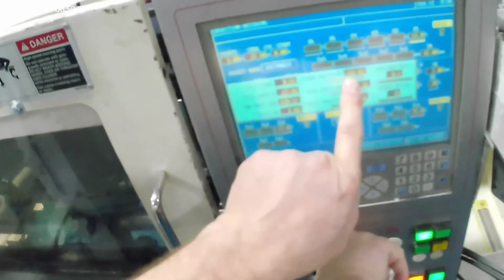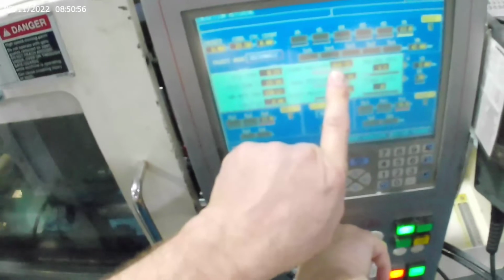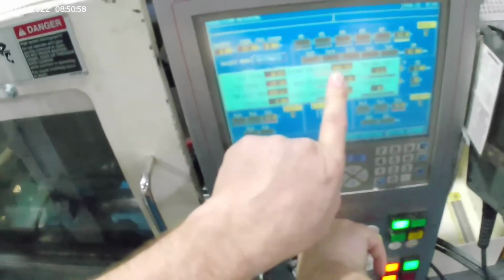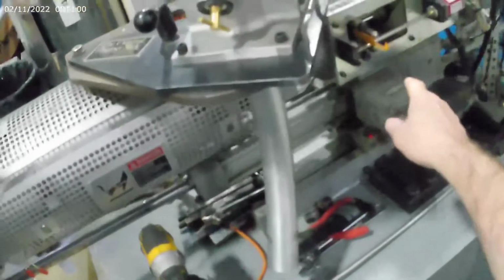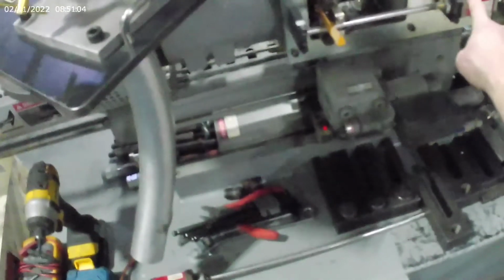If you look here, it's got a funky reading on your position. It goes to 0 for a minute. Watch it, I suck it back, run it forward, it does 0, but then it drops to a funky reading, a 664 reading, with my screw bottomed out. So I'm thinking maybe the transducer may be an issue. We're going to dig into that and see if that's the problem.